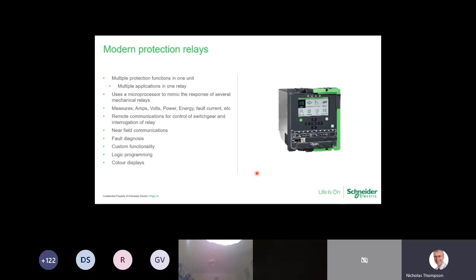You can also do a lot of diagnosis with these. So when we look at the fault diagnosis, what the relay is doing is recording a waveform as the fault is occurring, and you can set that for a very short time span, 1 second, or you can increase the amount of time that it's going to record, and you can extract that file out for a much more detailed analysis. You can also hook these relays up now onto communications network for remote monitoring, remote changing of the settings, and remote downloading of any event logs or fault analysis.